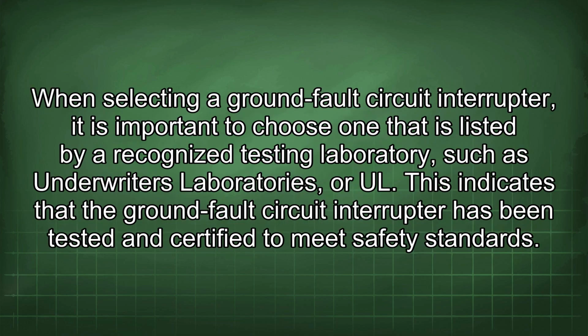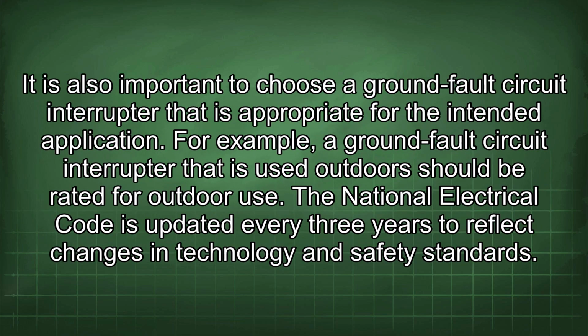When selecting a ground fault circuit interrupter, it is important to choose one that is listed by a recognized testing laboratory, such as Underwriters Laboratories, or UL. This indicates that the ground fault circuit interrupter has been tested and certified to meet safety standards. It is also important to choose a ground fault circuit interrupter that is appropriate for the intended application. For example, a ground fault circuit interrupter that is used outdoors should be rated for outdoor use.